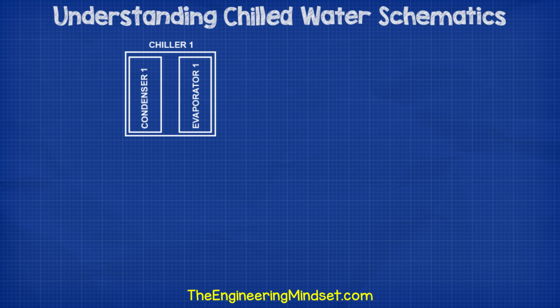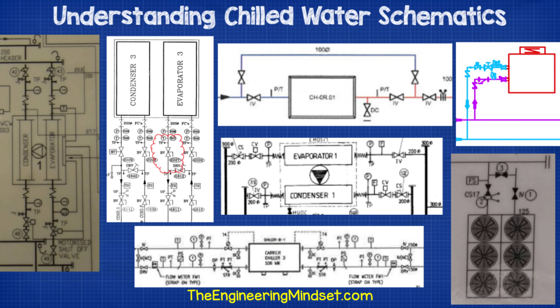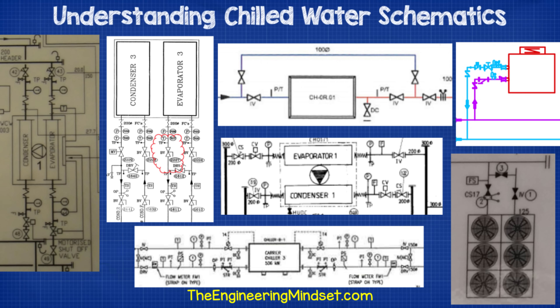So let's look around the system and each of the components to understand how it works. I've based this design off a real-world example for an older, constant-flow, water-cooled chiller system, as it's easy to understand. I'll show some real-world examples as we go through, and we can compare these to some different designs so that you understand the differences. We'll first start with the chiller — I'll just show you some examples of how chillers are illustrated on schematics, as it really varies. The two in the top right and the one in the bottom right are all air-cooled chillers, and the rest are water-cooled.